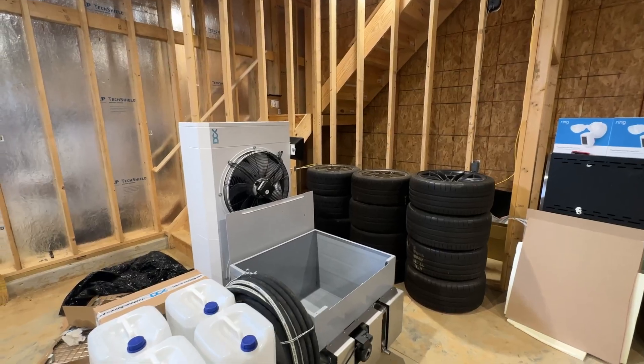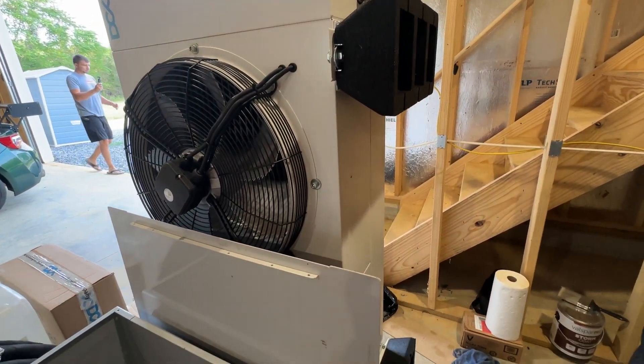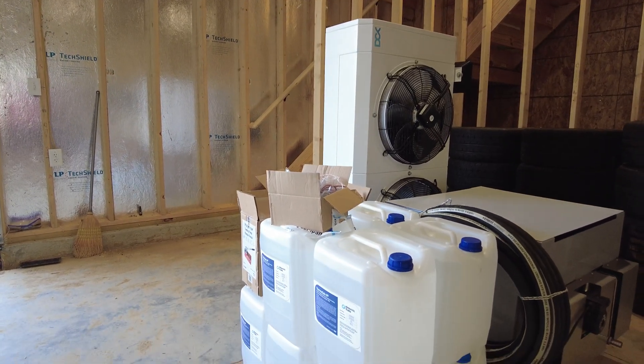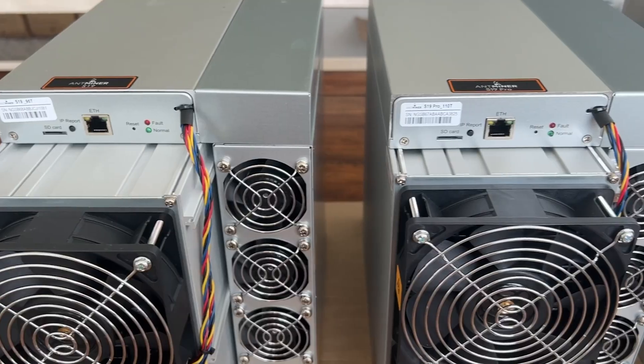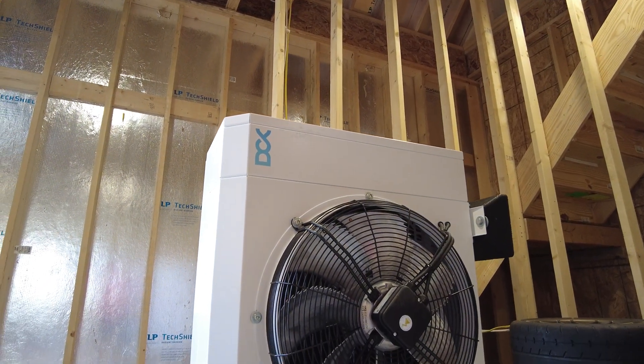Immersion, baby — it's finally here! We've got our first piece of immersion mining farm infrastructure that we're going to be deploying. This is a DCX system; they call this an enclosure, which is basically a big immersion tank that they make. Behind me is a dry cooler. A dry cooler is basically a big radiator. Bitcoin miners are custom computers — they sit in the fluid, and the fluid runs through that radiator outside. Hot fluid goes in, cool air flows over it, cooler fluid goes out. That's the simple essence of what we're dealing with.